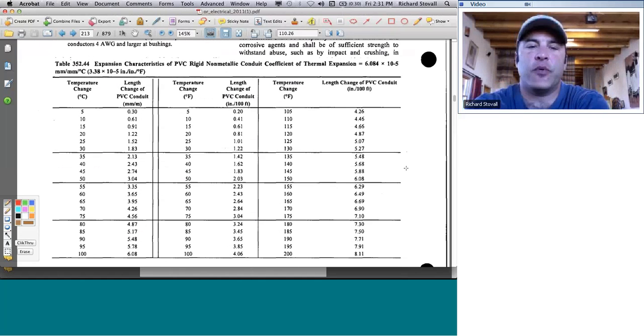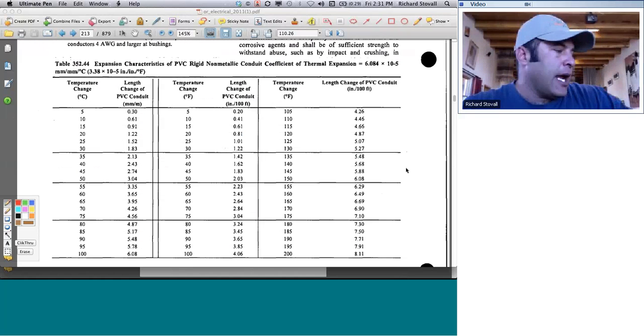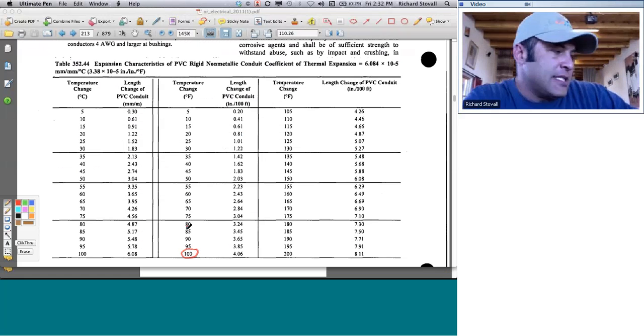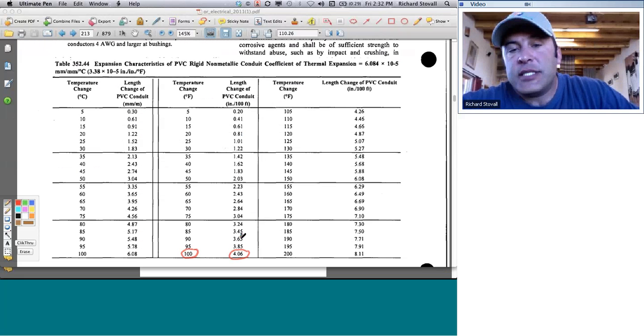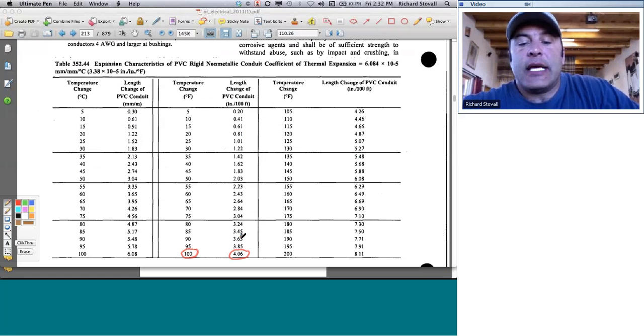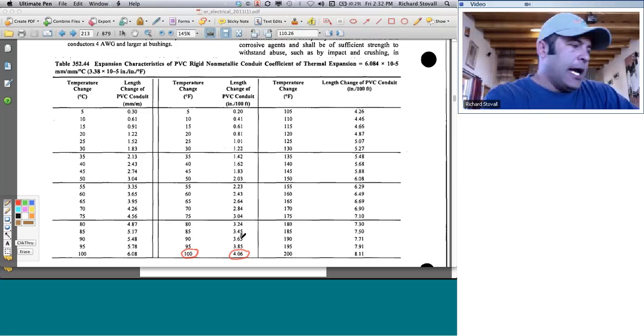Okay? So if the question is calling for a temperature range of, say, 100 degrees Fahrenheit for PVC, you can expect the length of change in the PVC conduit to be 4.06 inches. Okay? So you would need to have an expansion fitting that was greater than 4.06 inches, or you might choose to put two expansion fittings in the run, okay?